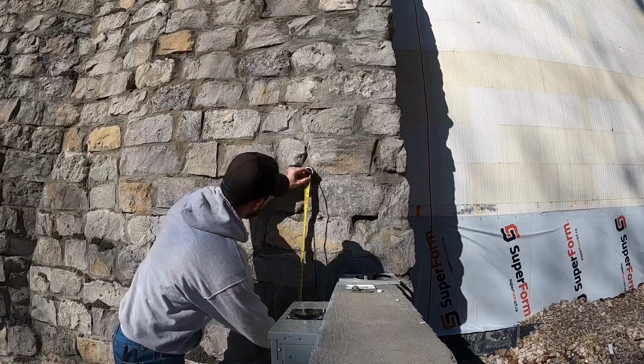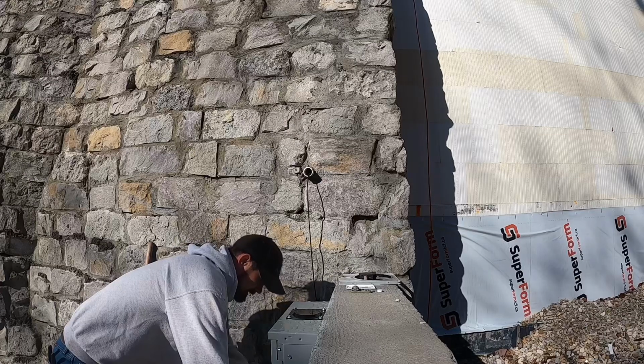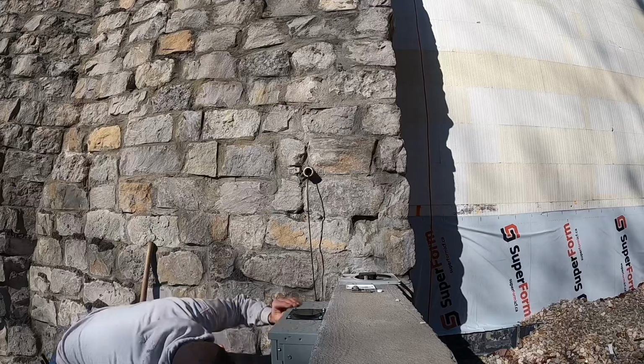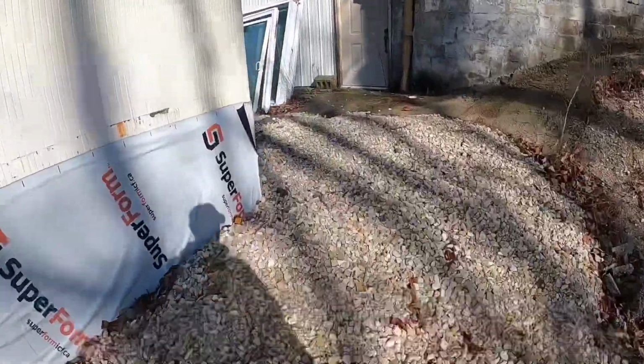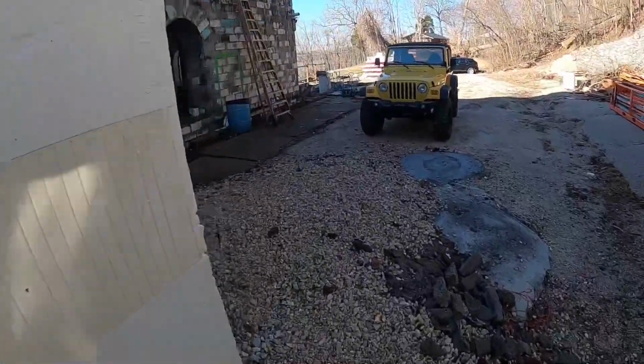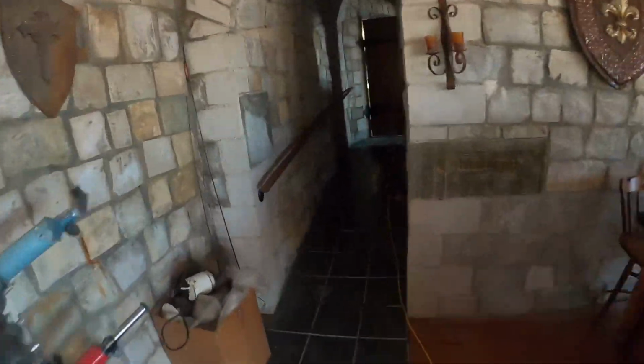And then we would be essentially another 4 feet. So that's 8, 10, 12 feet of wire on the outside. Now let's go in. When I say outside, that gets us some wire on the inside, but that gets us to the wall we have in here in the bathroom. So we know we need a minimum of 12 feet, and we know we need an internal 200 amp panel.